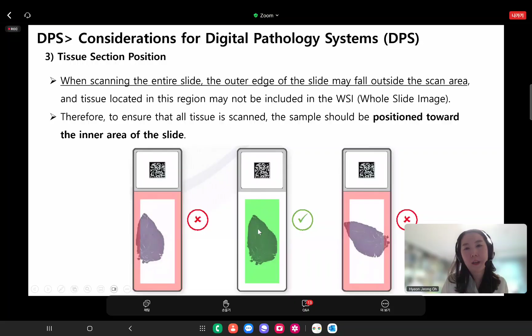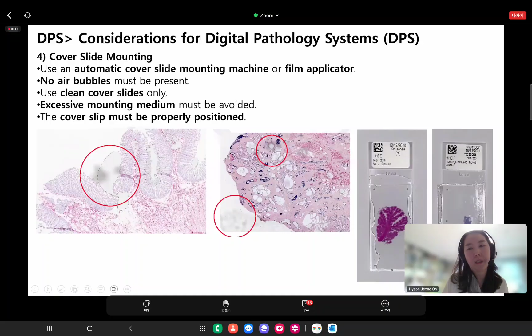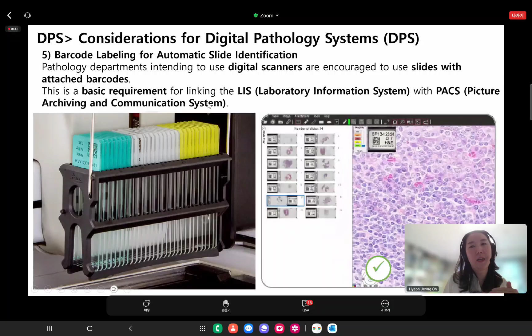The cover slide mounting is also critical. You have to use an automatic cover slide mounting machine or film applicator. And no air bubble must be present, and use clean cover slide only. And excessive mounting medium must be avoided, and the cover slip must be properly positioned because it can make the scanner stop. And barcode labeling for automatic slide identification is also required. It is a basic requirement for linking LIS with PACS. And each slide must have only one label.